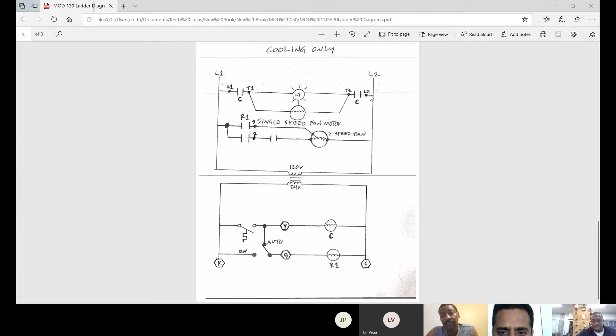Now we're going to go ahead and do L2. We're going to connect L2 to our transformer, and connect L2 to the L2 terminal on our contactor. Then here's my transformer neutral — I'm going to connect that and the one coming from my contactor, both on the same terminal.